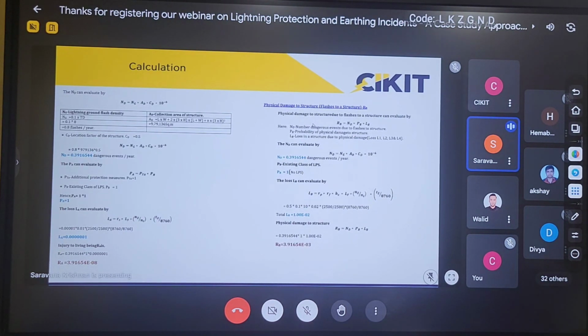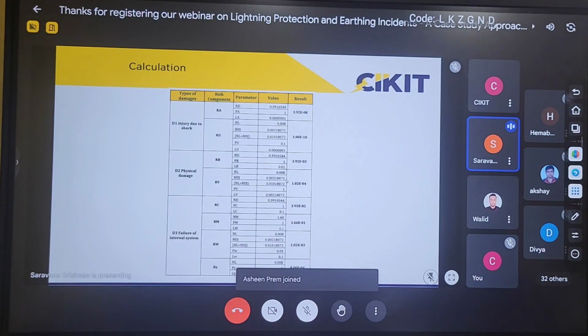So if I calculate R1, it will be the sum of four parameters: RA plus RB plus RU plus RV. Since RB is on the order of 10^−3, obviously the value of R1 will also be higher. So the risk due to lightning will be much higher on this particular building without any protection measures. Here we have considered the value of PB as 1 because there is no lightning protection system involved. So this is the value for the different parameters, and you can observe that it is much higher. So the risk due to lightning is much higher under these site conditions.